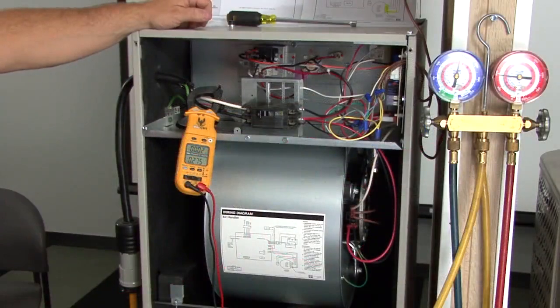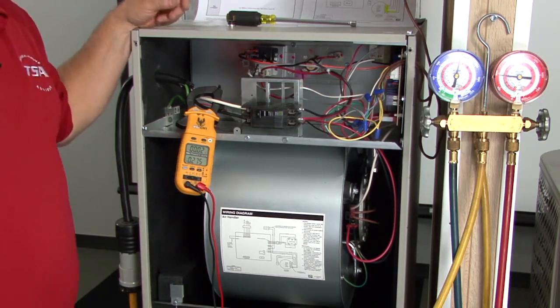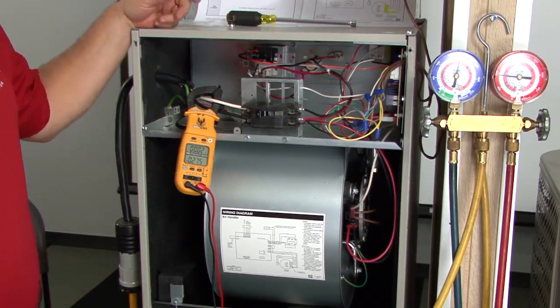Okay, so one of the things you want to do, every time I did a fall check, one thing I always made sure I did was make sure that backup electric heat works. That way I knew if the heat pump wasn't functioning, and the homeowner called me and said it was froze up or anything like that, I knew I could instruct them to go to emergency heat, and I knew from my fall check that that electric heat was working. So whether it's a new startup or an existing heat pump, you absolutely want to make sure that electric heat is working.